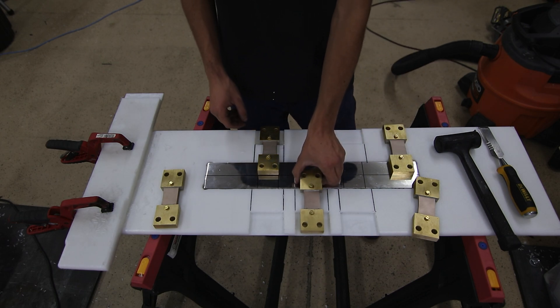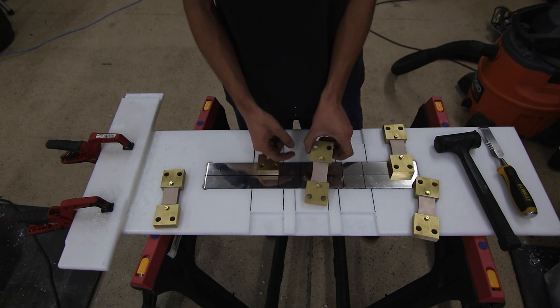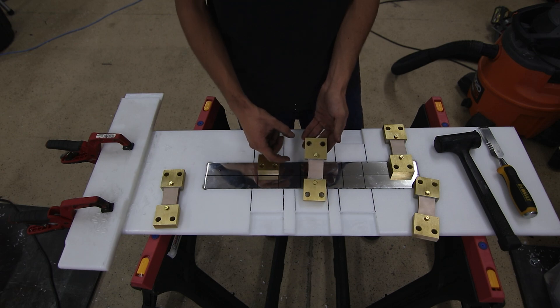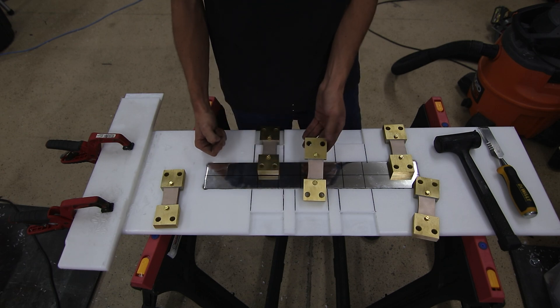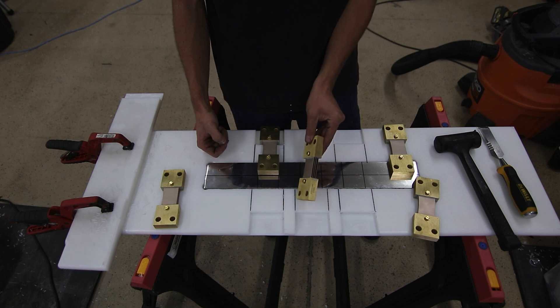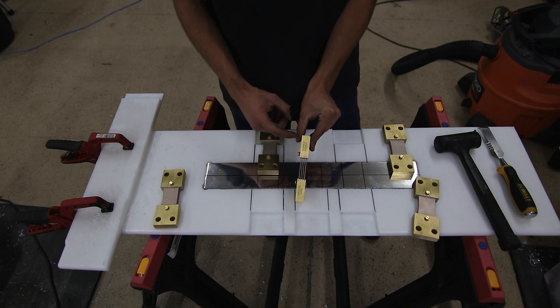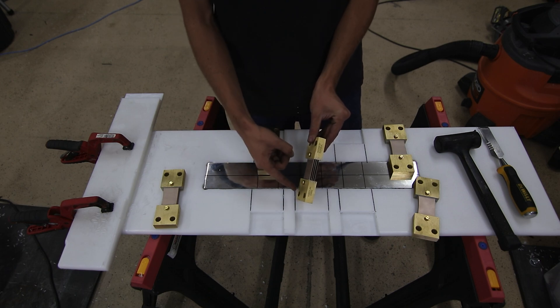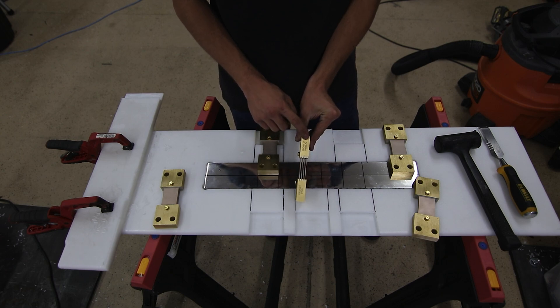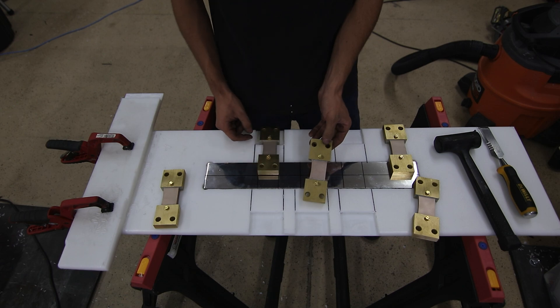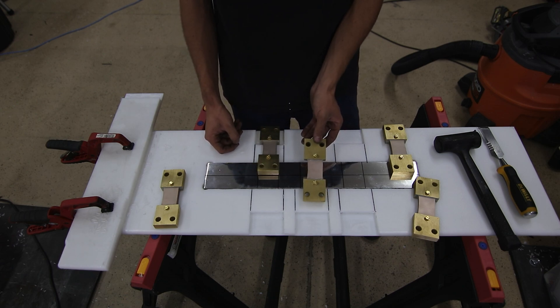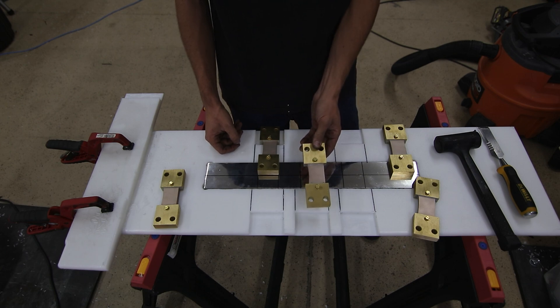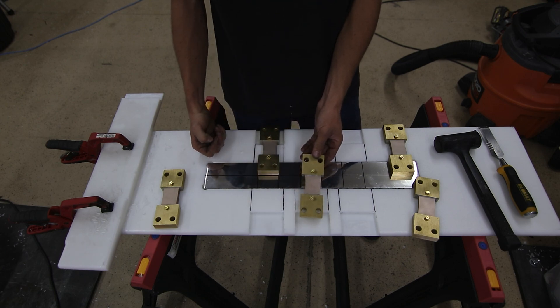Now what a shunt is, in case you didn't know, this is essentially a resistor. And it's a fixed resistance that correlates to a certain voltage drop at a certain amount of current. So if you're running 500 amps through here, it's going to drop 50 millivolts and it'll be proportional. So for example, at 100 amps, it'll be 10 millivolts. And that's measured on these two screws.